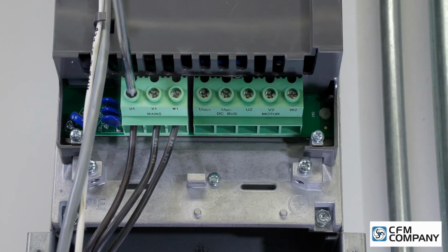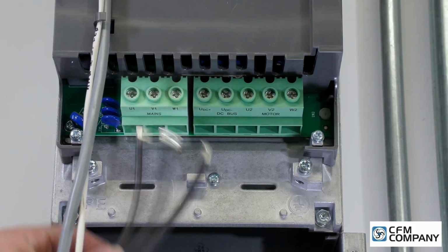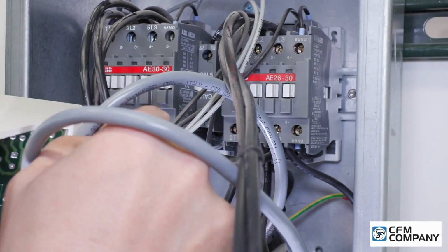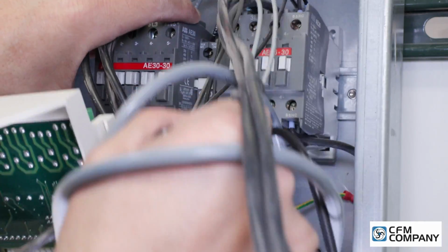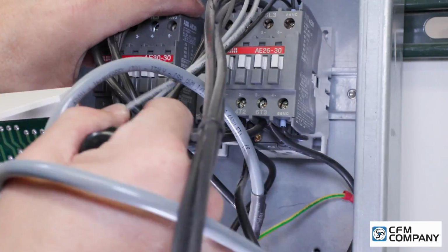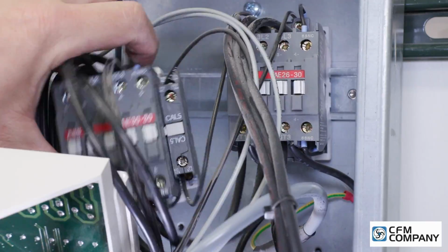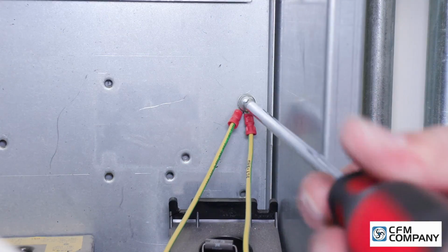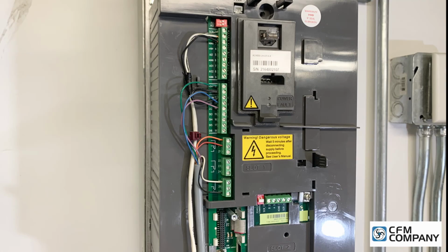Remove the three-phase conductors from the VFD input terminals U1, V1, W1, labeled mains. Next, remove both bypass contactor 2M and the drive output contactor 1M from the DIN rail mounted to the backplate. Remove the ground wires connected to the backplate. Use a cell phone camera to take pictures of the control wiring.